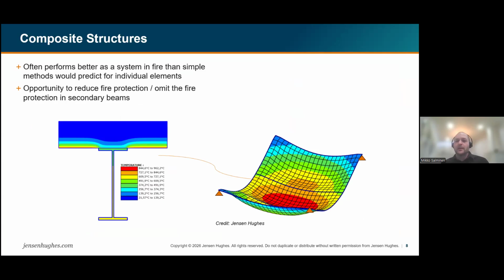That's a really good structural system for fire, because often it performs much better as a system than simple methods would predict for the individual members. That gives an opportunity to reduce the fire protection in some of the members, especially the secondary beams. So even if the deflections are high in the structure, it still has the resistance if it's designed correctly, like this one here.